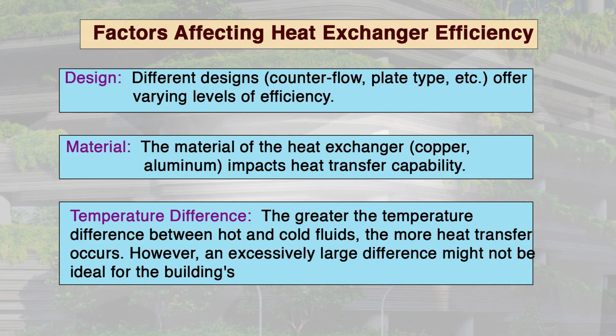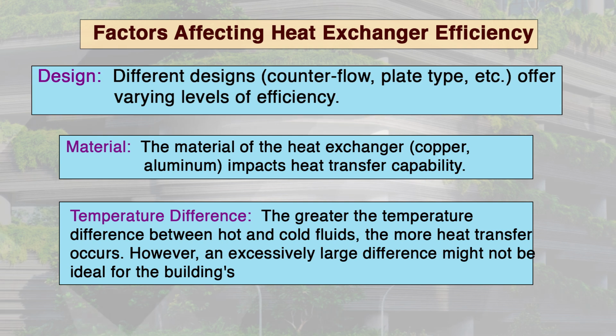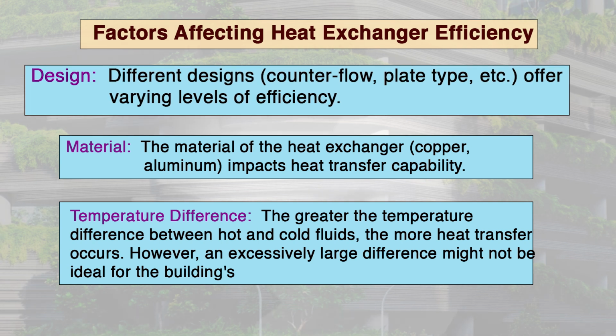This slide highlights the key factors that influence how effectively a heat exchanger performs its job. The three factors that affect heat exchanger efficiency are design, material and temperature difference. First, we will see design. The design of the heat exchanger plays a crucial role. Counter flow designs, where the hot and cold fluids flow in opposite directions, are generally more efficient than parallel flow designs. Plate type heat exchangers, with their large surface area for heat transfer, often outperform shell and tube designs in terms of efficiency and size.